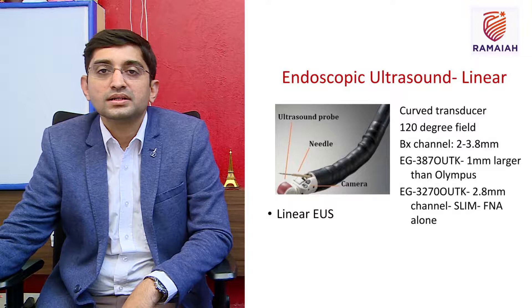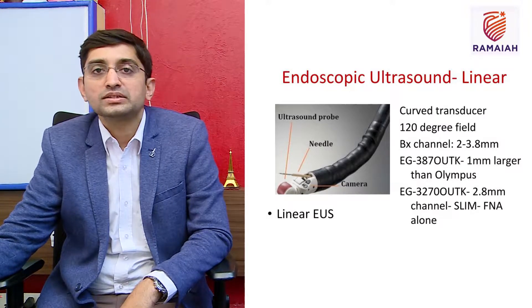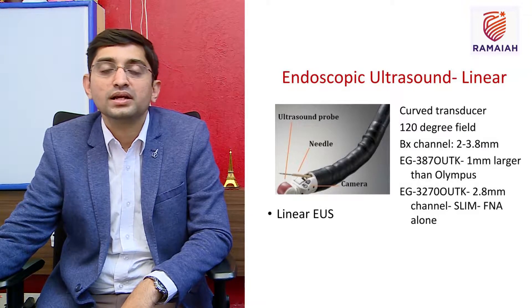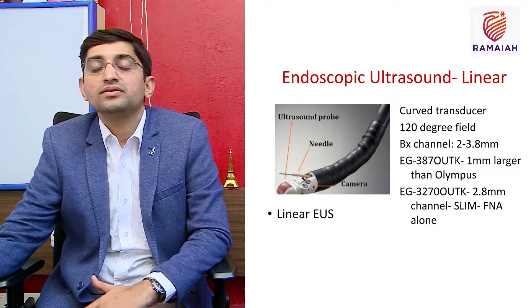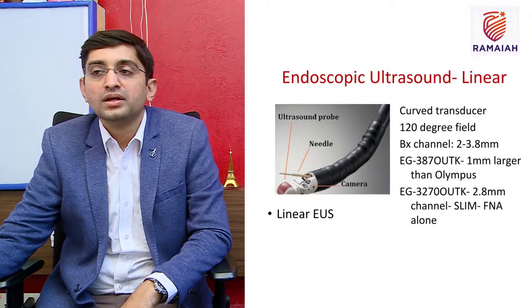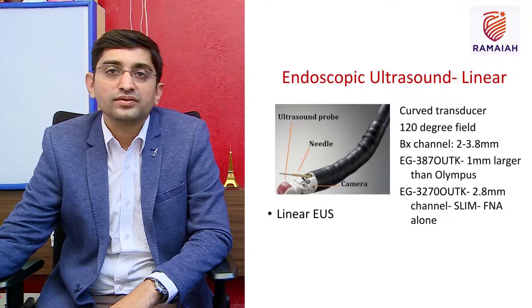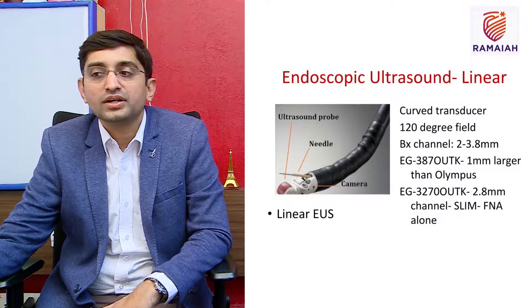A linear echo endoscope has a convex array at the tip, giving a picture similar to an ultrasound image. A radial echo endoscope provides a sector-based picture similar to computed tomography. The advantage of the linear echo endoscope is its curved transducer, which gives a 120-degree field of vision.